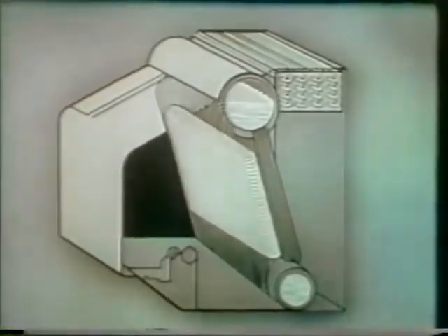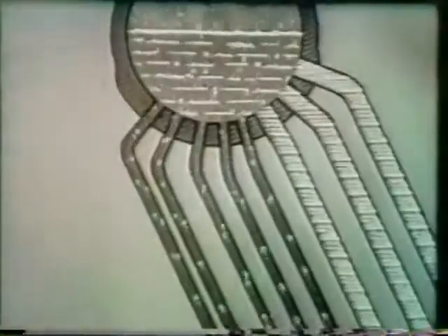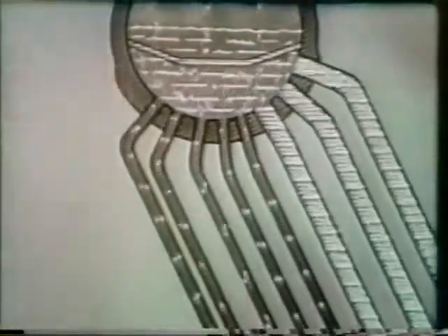In the superheater, saturated steam becomes superheated steam. This steam has a higher temperature, but approximately the same pressure as the saturated steam entering the superheater from the steam drum. The end point of moisture carryover is reached when the total capacity of the baffles and other moisture-removing devices cannot bring carryover below tolerable limits.